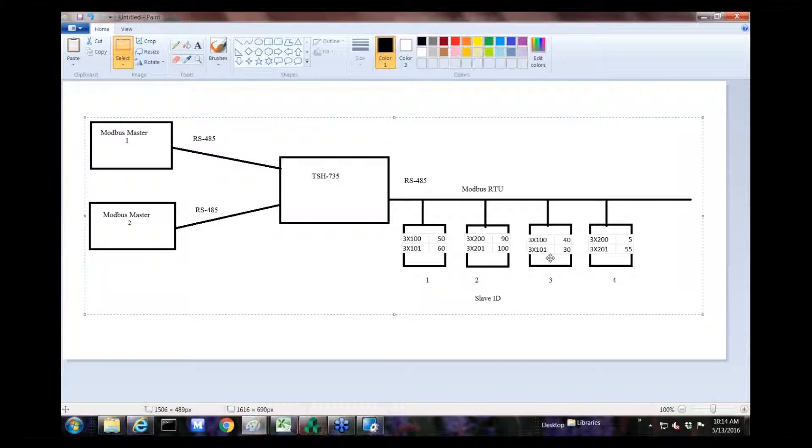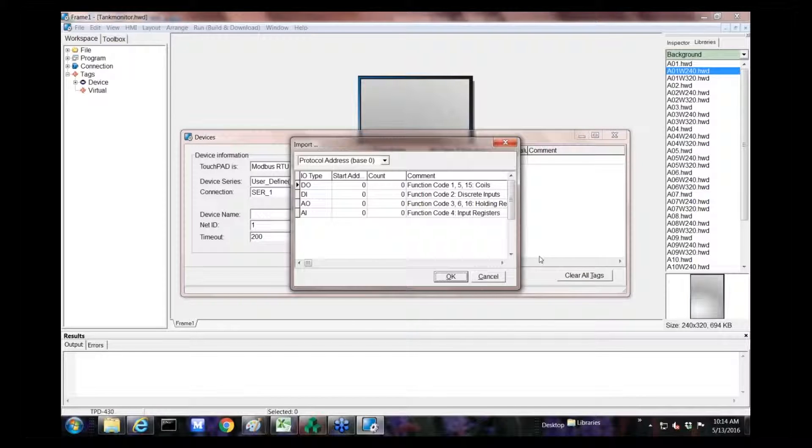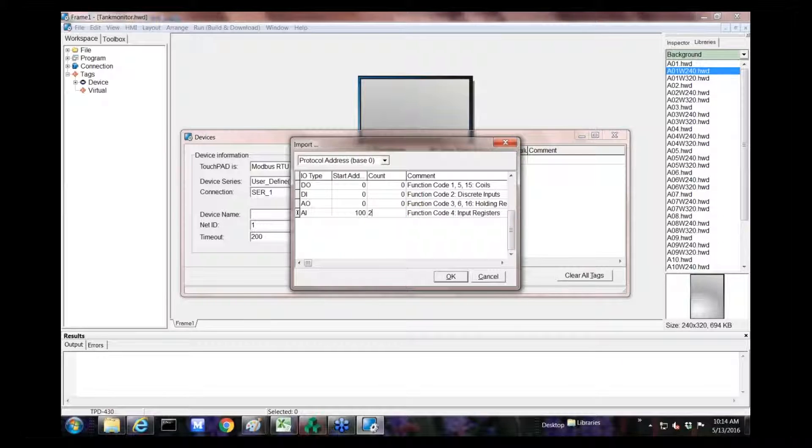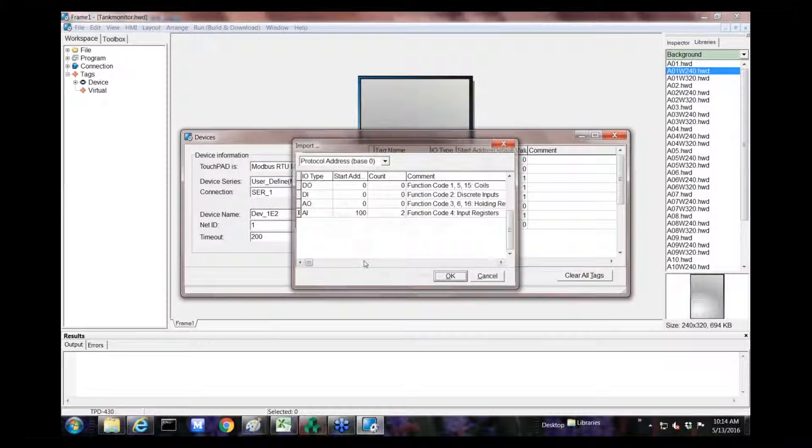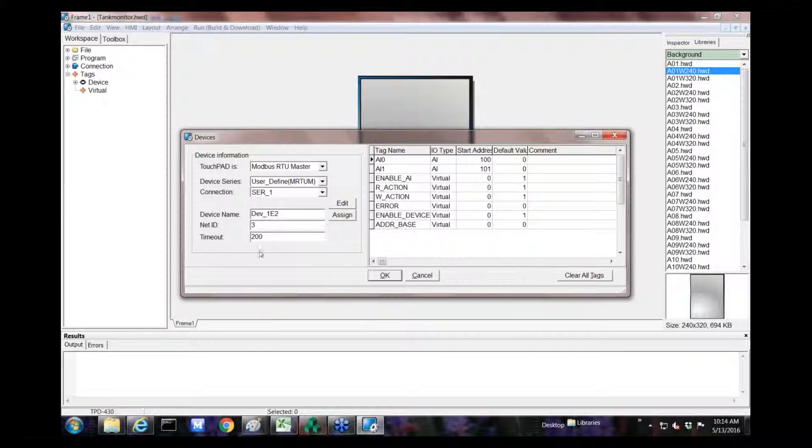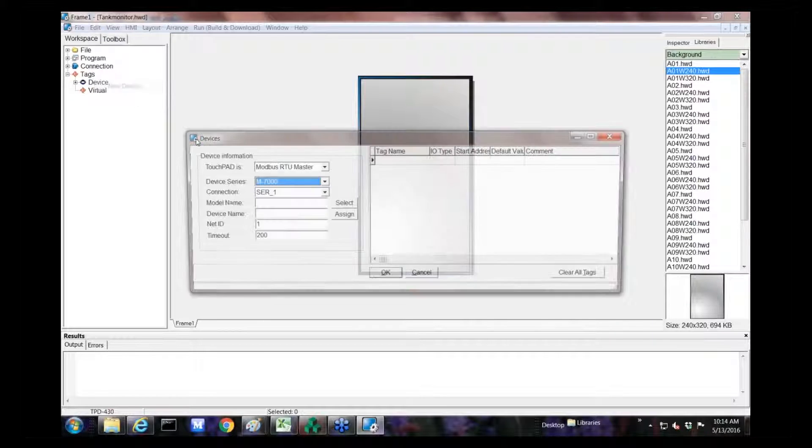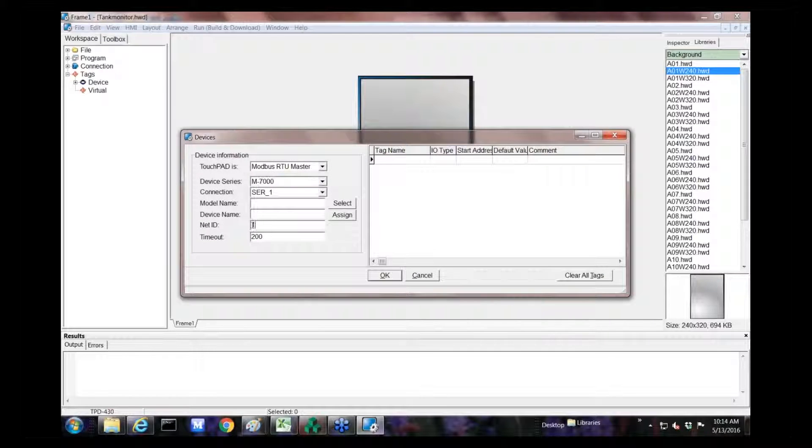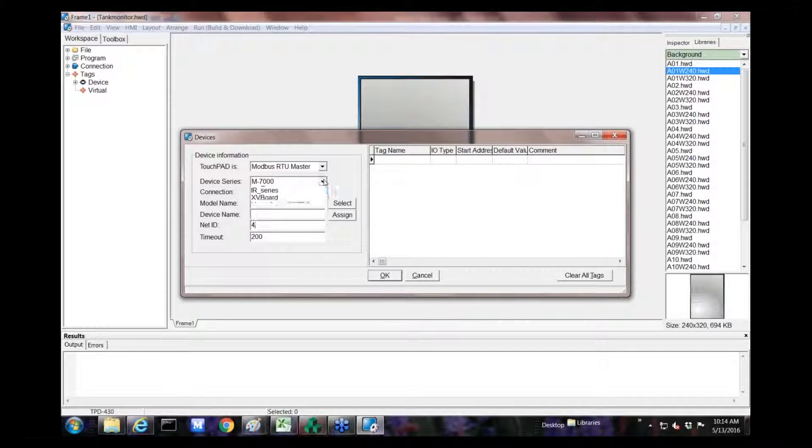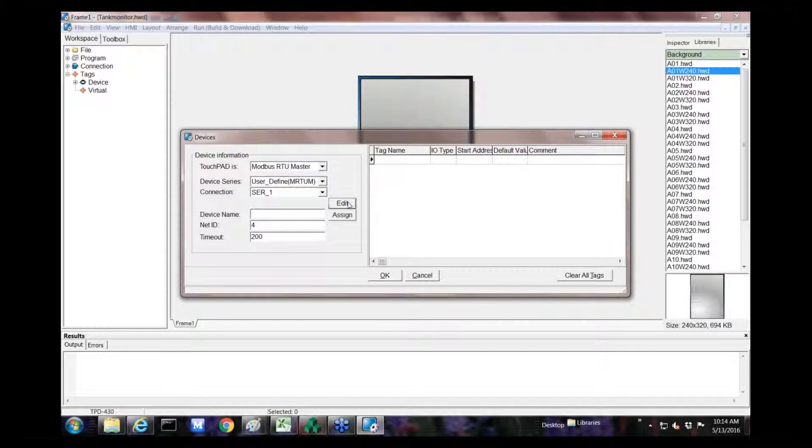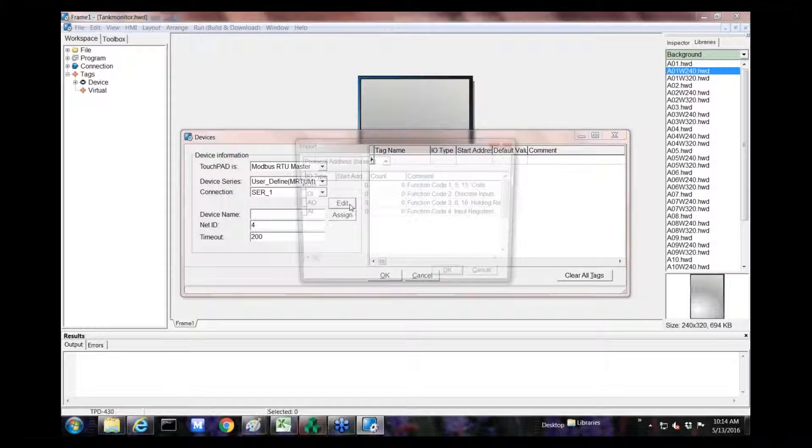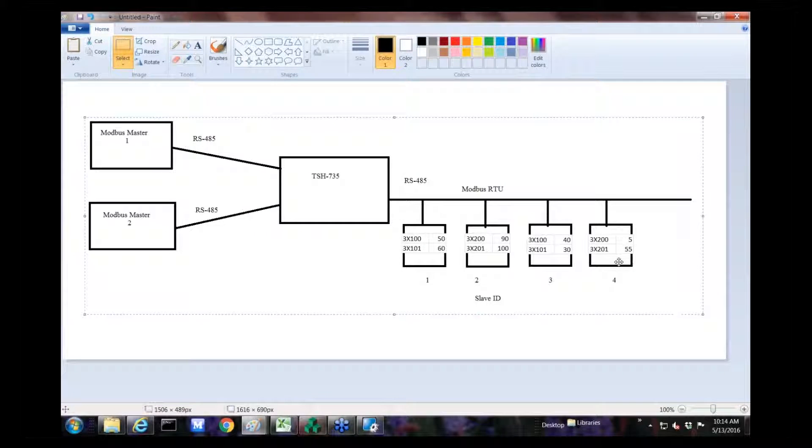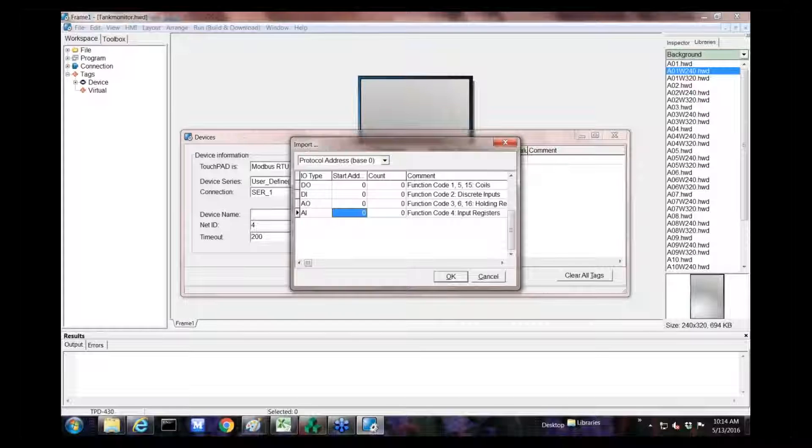Let's just assume they're third-party devices with no properties. This one, reverting back to my picture, first slave address is 1, and we're pulling register 100 and 101. So we go to start address of 100, and we're going to do two registers, and the net ID is 1.